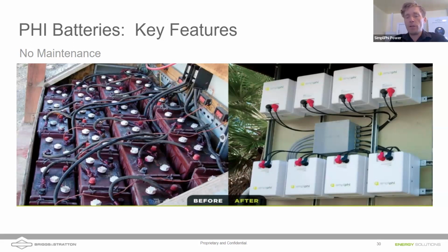However, it doesn't take very long for that battery to heat up. The internal resistance of the battery is a bit higher at cold temperatures, and the reason for that is the electrolyte is fairly viscous. That means as those lithium ions are moving through the electrolyte, they're giving a little more of their energy to the electrolyte, causing it to heat up. So if you're charging at 20 amps in the 30-degree Fahrenheit range, you'll quickly move that battery temperature up to room temperature, so it wouldn't charge at that rate for very long. I think that's a good question - was it Paul or Daniel that asked?